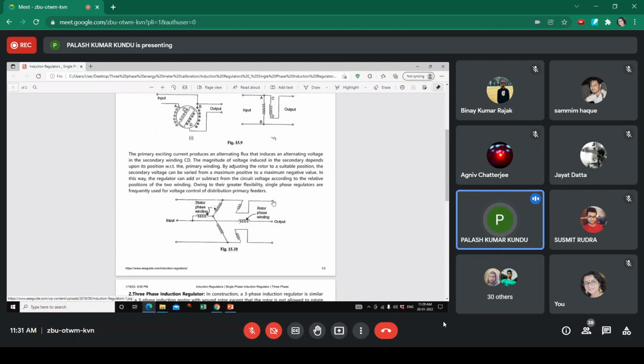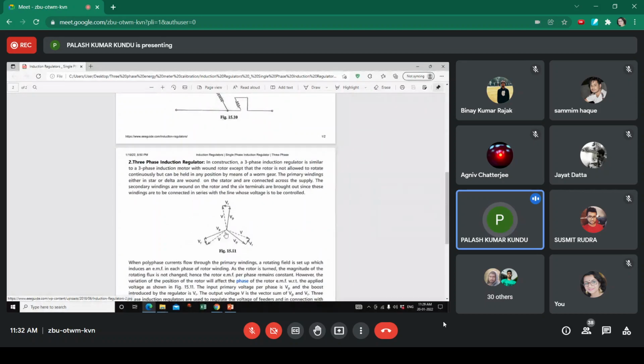The final winding, which is a three-terminal or three-phase winding, consists of two induced voltages. One is the primary winding voltage, and the other induced voltage is the phase shifted secondary winding voltage. So these will be vectorially added, so that with respect to the common point, according to the phasor diagram, we get the resultant voltage V. V is the secondary voltage, which is called the phase shifted voltage with respect to the primary winding voltage Vp.